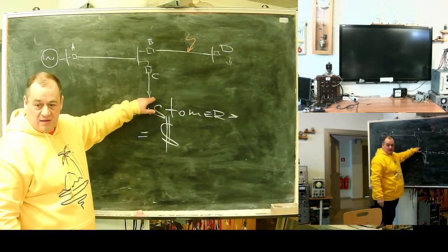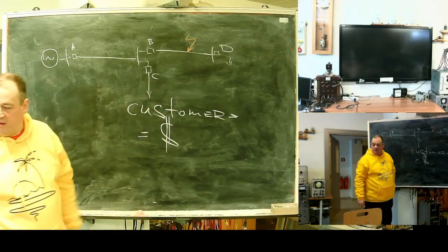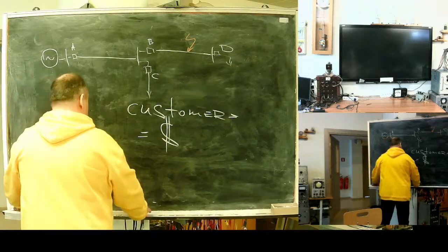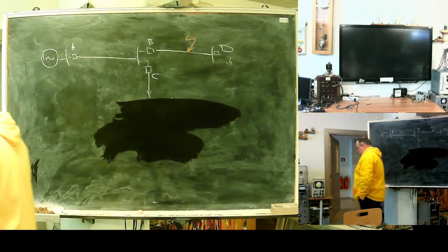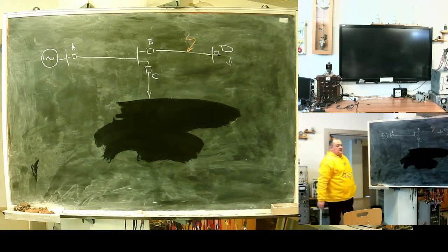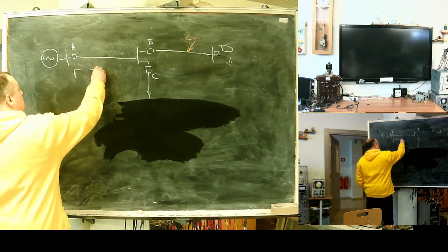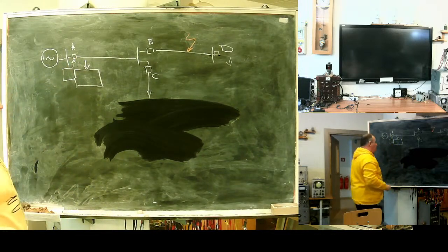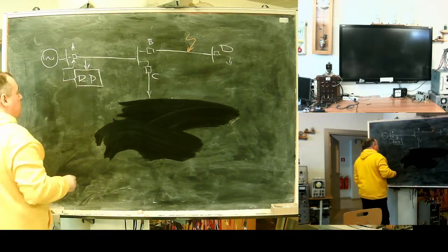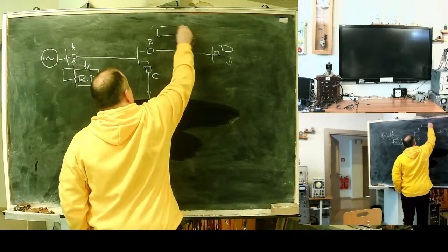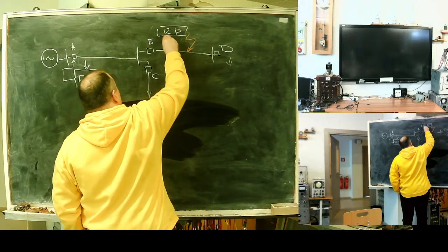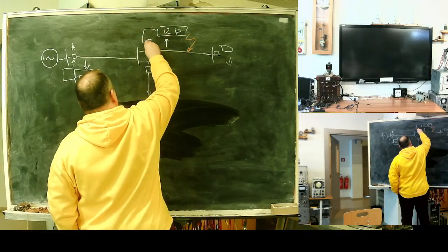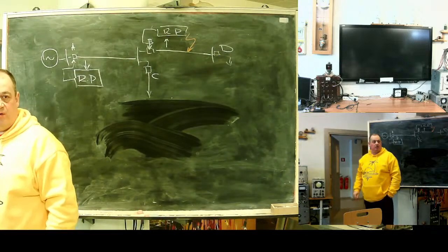If I disconnect a customer without necessity, not good. So here we are coming to the idea: protected zone. I need some device monitoring the line and sending a signal to disconnect. Relay protection. I also need it here. Relay protection takes some information from my line, and if the line is damaged, sends a disconnect signal.